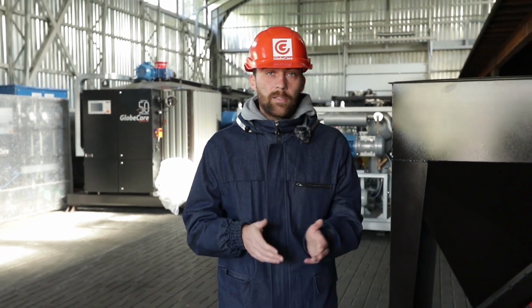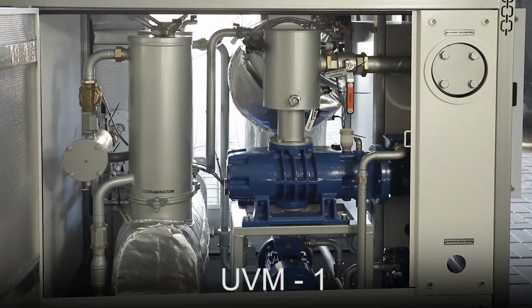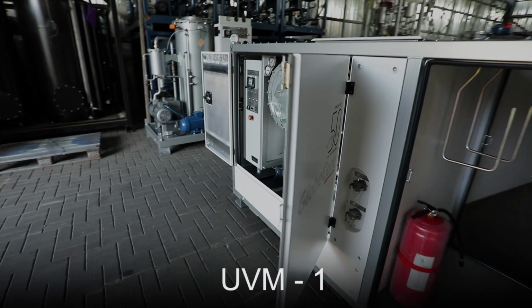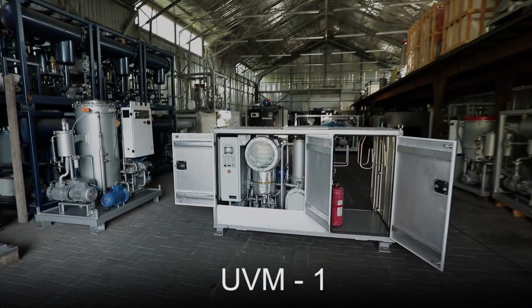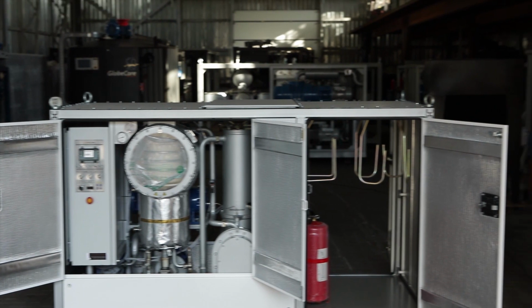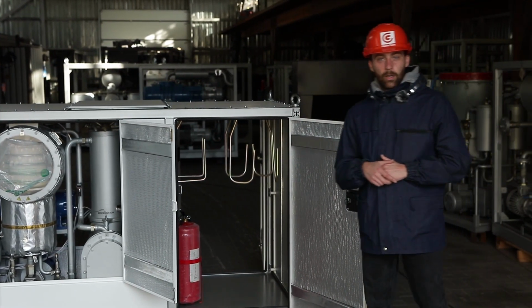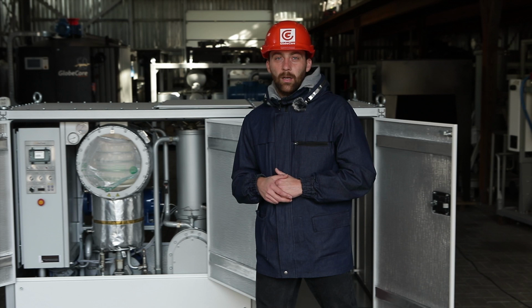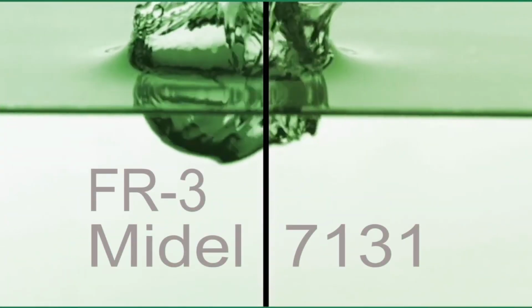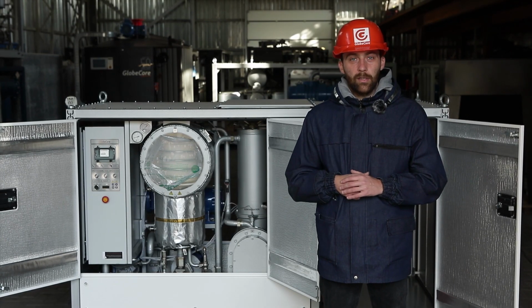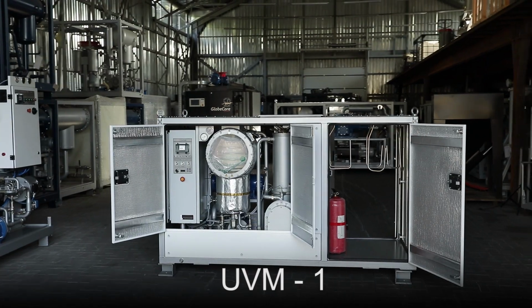Fire-resistant dielectric liquids, like petroleum oils, are contaminated, moisturized, and oxidized by atmospheric oxygen during storage and operation. For this reason, unwanted impurities must be removed from them on a periodic basis to maintain high-quality insulation and reliable operation of the transformer. GlobeCore has developed the UVM-1 unit, which can be used to purify not only petroleum transformer oils, but also fire-resistant dielectric liquids of vegetable and synthetic origin, FR3, Midel 7131, etc. The capacity of this unit is 1 cubic meter per hour.